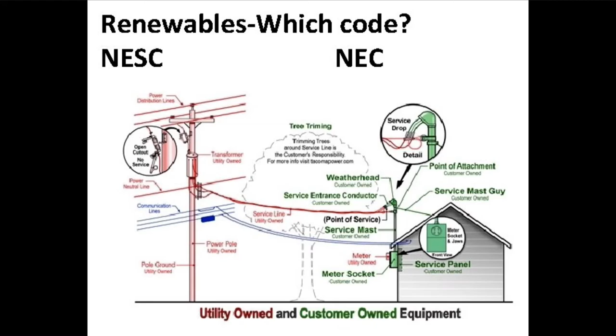That point will have to be grounded according to their requirements. What you do on the other end of that line, 10 miles down the road, they're less worried about. So the switchgear and all the concerns happen at their service point. That's typically how things work, the utility is focused on their service point and requirements there. Once they take off, it's the engineer's job to determine how things are grounded from there on out, which comes down to the engineering.